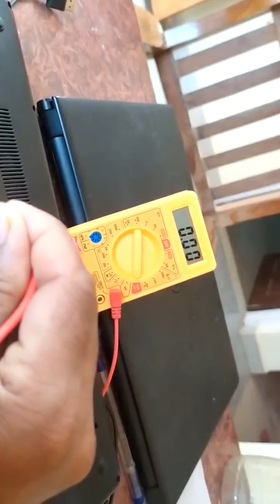Now what is to be done? These two leads need to be short circuited. We put the probes, one black to the common and the red to the ampere port, the 10 ampere port. Now we go to the 10 ampere setting, keep it there.